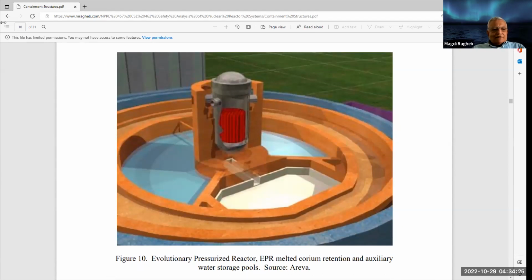Here is some detail about the design. They suggest that if your core melts into molten metal, it could breach the pressure vessel at the bottom and leak. They don't want it to get into the ground and interact with water in the concrete, because if molten metal interacts with the concrete base mat of the reactor, it can release lots of steam, since we cure concrete with water, and it will also release hydrogen. So what they do is have a core catcher that catches the molten core material, the corium, and spreads it in a pond with a large surface area to radiate its heat to the environment.